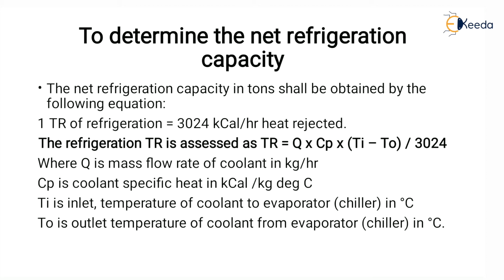So the net refrigeration capacity in tons of refrigeration shall be obtained by the following equation. That is, 1 TR of refrigeration is equal to 3024 kilocalorie per hour of heat rejected. So the refrigeration TR is assessed as, where TR is tons of refrigeration, TR equals Q into Cp into Ti minus T0, divided by 3024, which is 1 TR of the refrigeration.